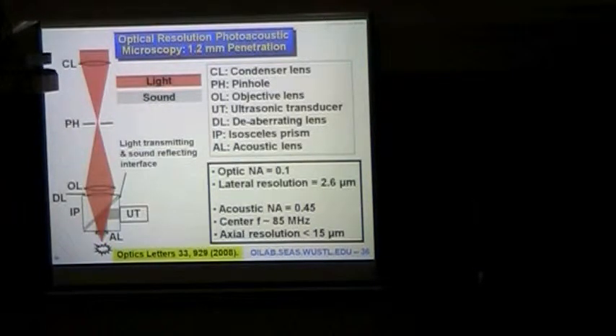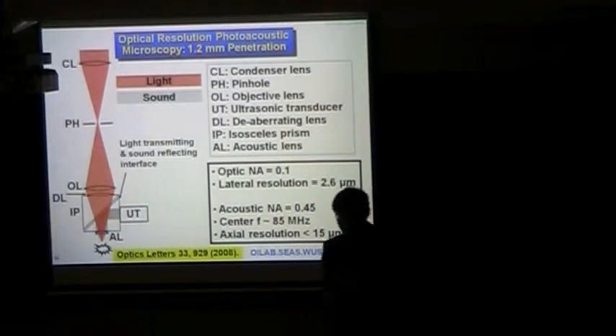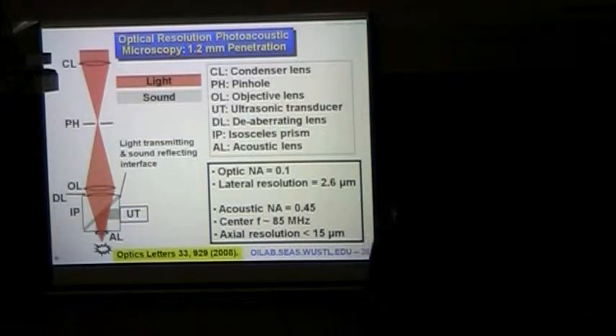We use this light-sound combiner made of 2 prisms separated with a gap. The gap is filled with liquid. So along the optical axis, the refractive index is well matched, which gives you very high transmission of light. However, at this solid liquid interface, the acoustic impedance is highly mismatched, which gives you a very strong reflection of sound. That's why the photoacoustic wave coming back will be reflected toward this ultrasound transducer.